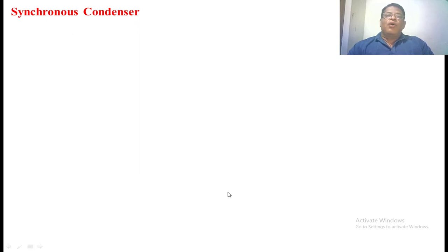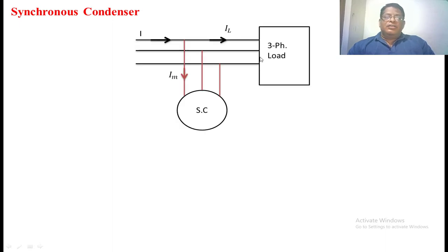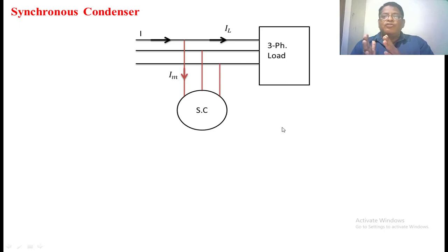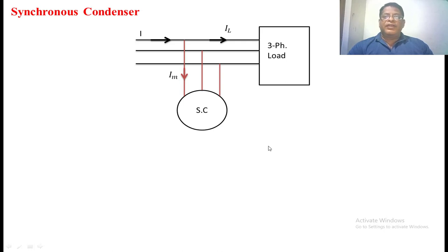A synchronous condenser is nothing but a capacitor, and an over-excited synchronous motor acts as a synchronous condenser. We use a synchronous condenser in power systems to improve the power factor. When an AC inductive load is connected, it requires both real power and reactive power, and the reactive component current dominates, lowering the power factor. By connecting an over-excited synchronous condenser across the load, it operates at a leading power factor and supplies the reactive power locally required by the load. This reduces the reactive power that needs to be supplied by the source, thereby improving the overall power factor.